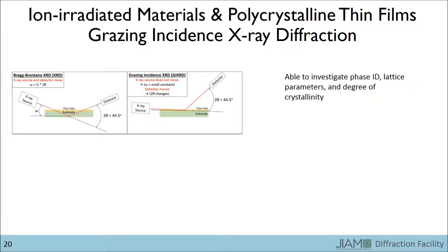As shown in the right panel, we can then hold the incident angle constant while the detector rotates through 2 theta, thereby keeping the penetration depth constant throughout the experiment. This is called grazing incidence X-ray diffraction. Our users regularly utilize this technique for phase identification, lattice parameter calculation, and the determination of the crystallinity of their samples.